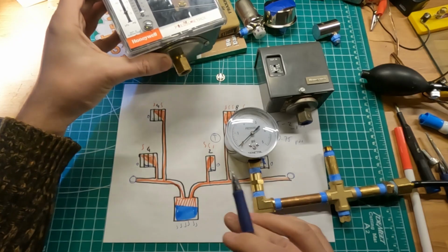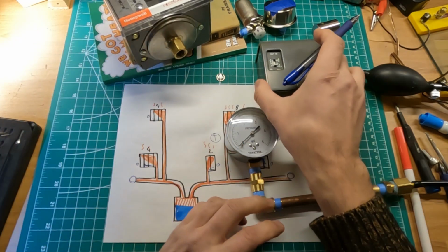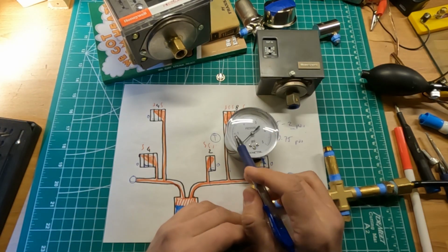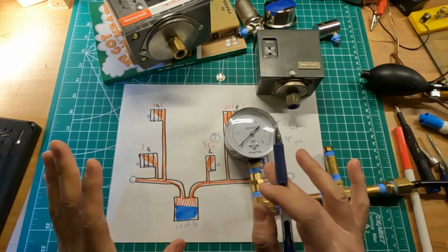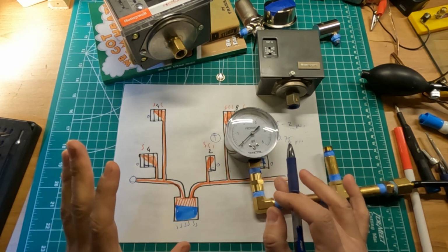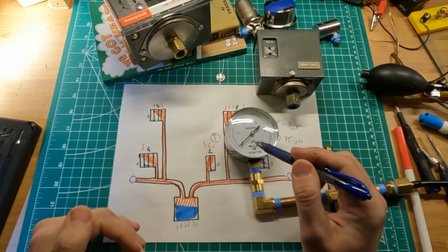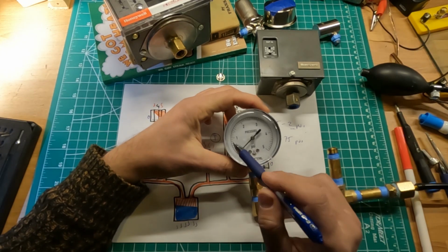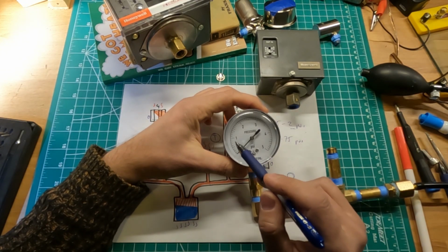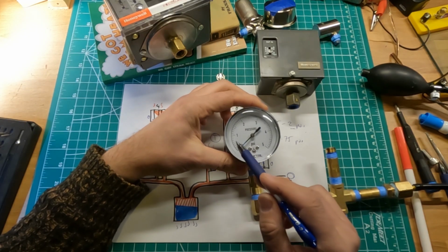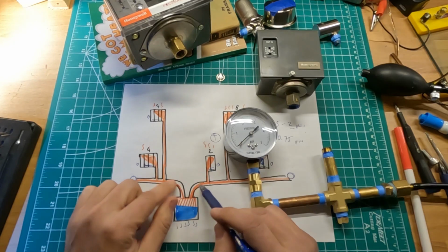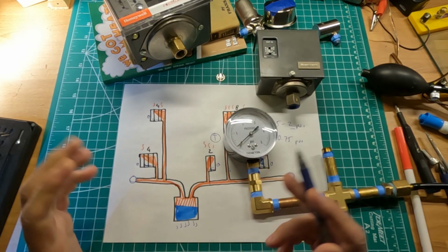So you can theoretically work with those Pressuretrols below 1.5 psi, but it's not advisable. So the next step for me is to get a Vaporstat, partially so that I don't get this extra, let's say, 2.5 to 3 minutes of working time when the boiler keeps on producing pressure, because the steam has nowhere else to go at that time.